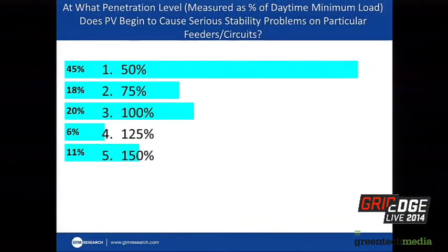Okay, so I'm not going to pretend to be a power engineer, so instead I'm going to go with the Tom Bialik answer, because it's just the answer based on actual data that we have. I voted for number one because, it's kind of different than what you said though, we have seen issues at 30% at the end of a circuit, and significant out of compliance issues. It's just factual data that's been measured. So it is what it is. Is that the minimum load, percentage of load? That's when it happens. It happens when we have a minimum load, but a nice sunny day. Well, right, a good sun, but the marine layer getting burned off. So when we see it, it plays havoc with our system.